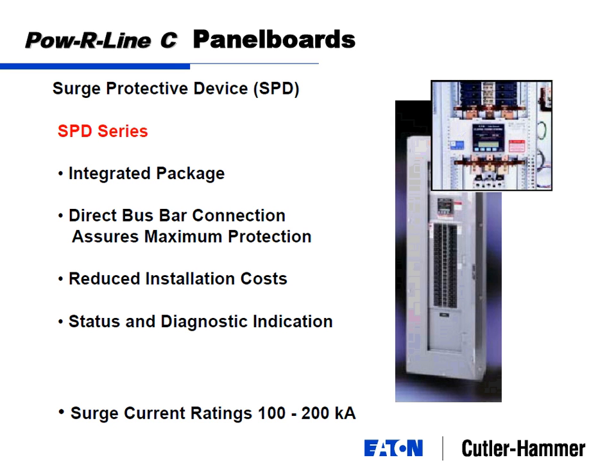Mounting it right in the panel keeps it nice and clean. It's a change-outable device. Direct bus bar connection right into a panel board. One of the things for these to be effective: inside of this SPD is what they call MOVs, metal oxide varistors, which are the things that work quickly and shunt the energy to ground.